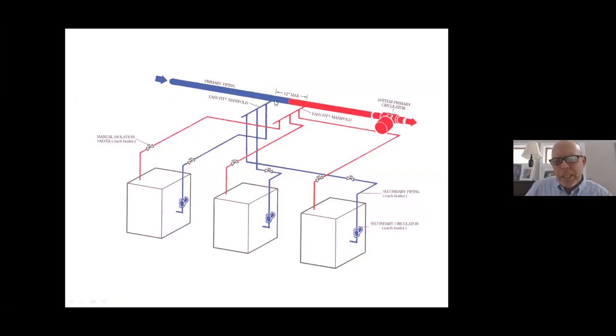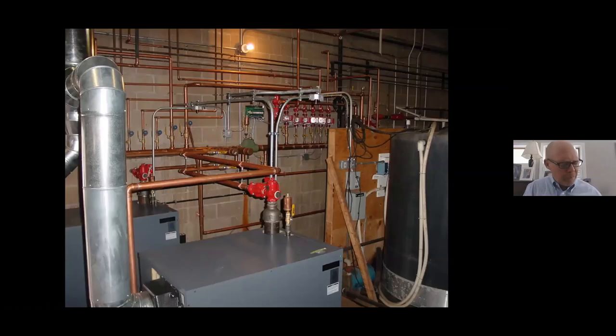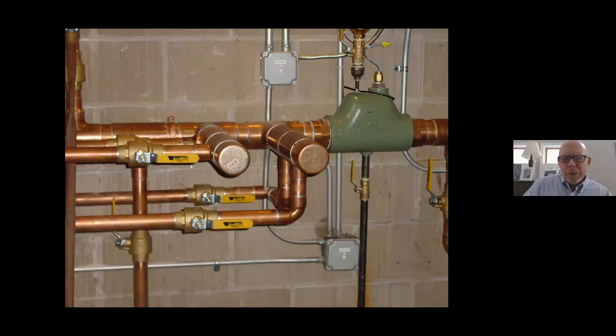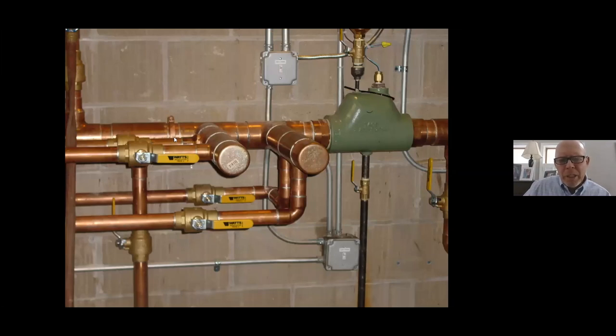The best way for a multiple boiler system is to use a manifold with one set of closely spaced tees, and individual takeoffs to each boiler. The benefit is that all boilers receive the same return temperature — you're not doing the blended cascading like in the one-pipe primary-secondary. Here's a field example showing two large oil-fired boilers with closely spaced tees, so whatever return temperature exists is the same for both boilers. Each injects its temperature rise into the supply pipe. This is the best approach whether you have modulating condensing, oil-fired, or atmospheric boilers.